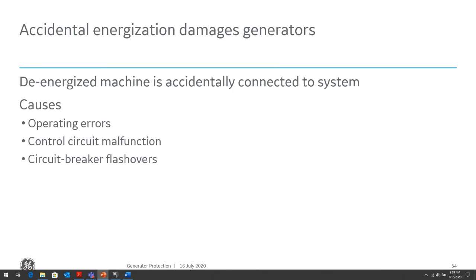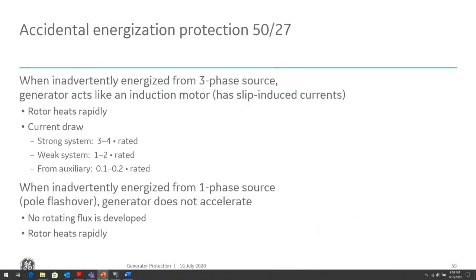So the cause of inadvertently energizing the machine is operation error: somebody inadvertently closed the breaker without the machine being ready to come online, or a control circuit malfunction, or flashover across the circuit breaker even though the breaker is open. Maybe there are issues within the breaker mechanism, or moisture in the circuit breaker, and it can cause flashover, which will then cause power to go in the direction into the system, into the machine. So the machine is going to be drawing current.